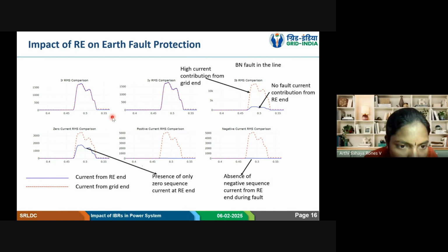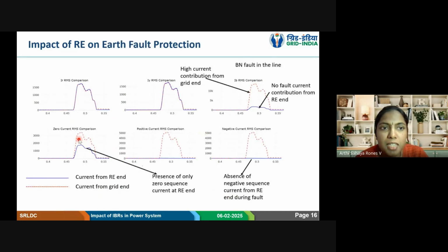So if we see here, the zero sequence current has gone as high as 1.8 kilo-amp. So 1.8 is a very high pickup for an earth fault protection to operate. So in this case, the high set earth fault protection operated because of this zero sequence current at the RE end. So that is regarding the impact of RE on the earth fault protection.